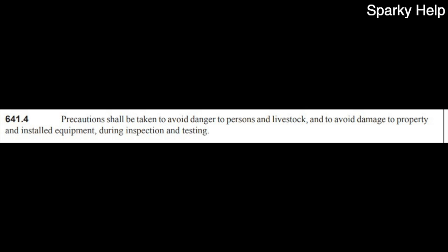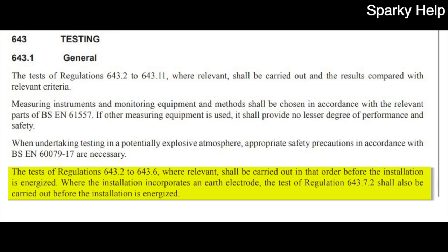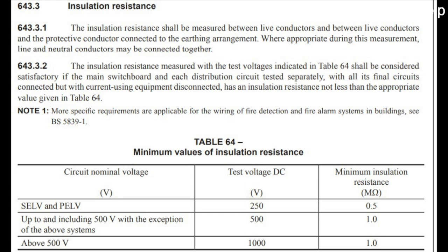So a small regulation, but one not to be ignored ever, because you should never actually damage the installation which you're about to test, especially as we're about to put 500 volts down the circuits. This regulation then tells us that we should carry out the test before energizing the circuit, and that all tests must be carried out in order, as suggested by the regulations here. So what does this regulation tell us? Well, the first regulation on here just basically tells us to test between live conductors and between live conductors and the protective conductor, but most importantly it says connected to the earthing system.